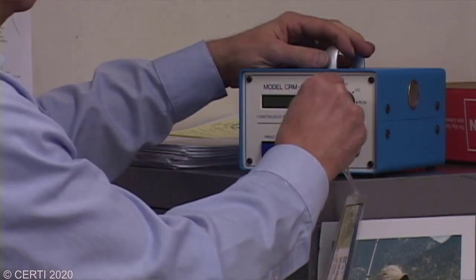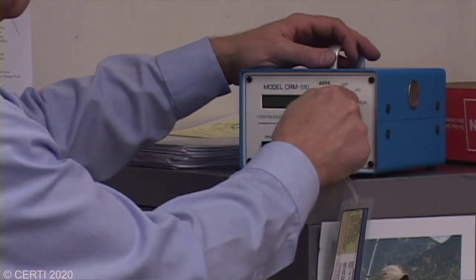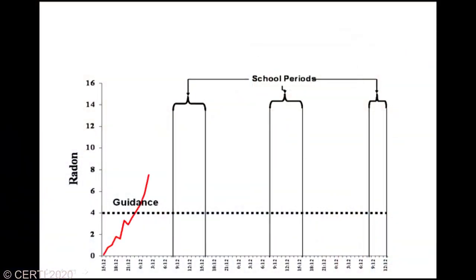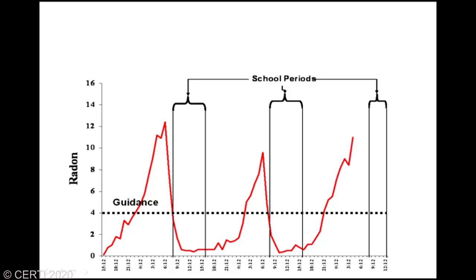If an HVAC issue is not obvious and there's an energy management system in the building, it would be prudent to have a radon professional deploy a continuous radon monitor in one or more rooms that have demonstrated high radon levels. By doing so, you can determine what the actual radon exposures are during occupied hours. You may learn that your HVAC system is already fixing the problem, or maybe you need to set the timers for the controls to come on a little earlier or shut off a little later, depending upon when students and staff are present, including janitorial staff.